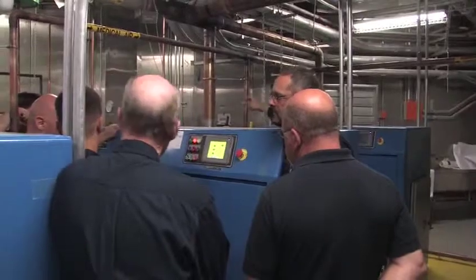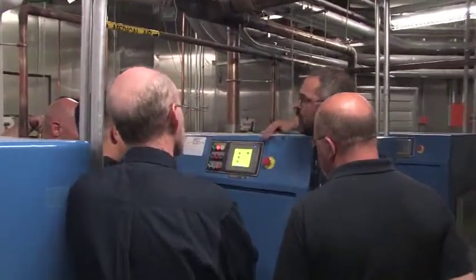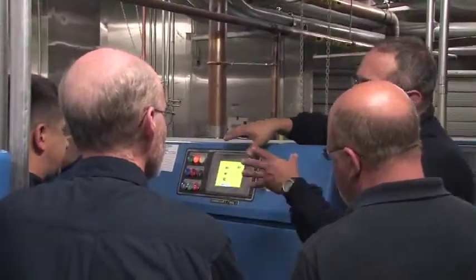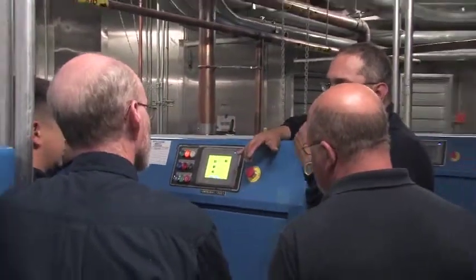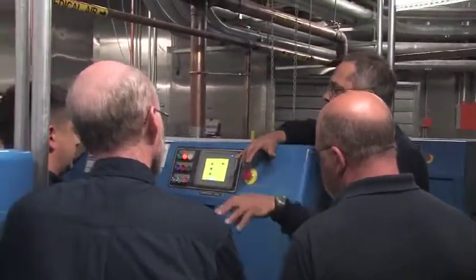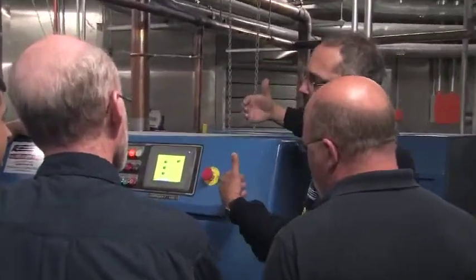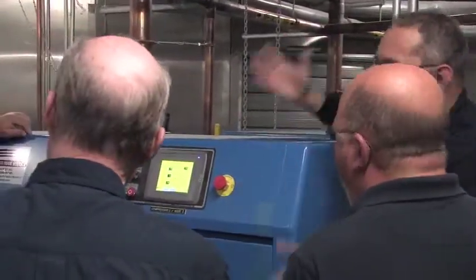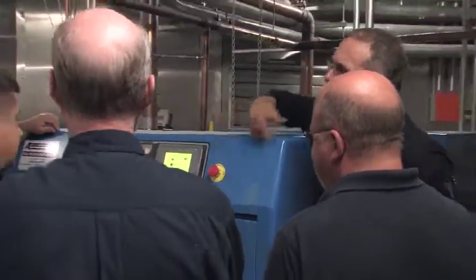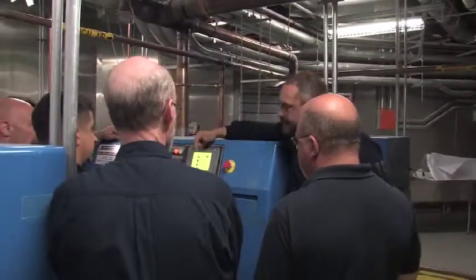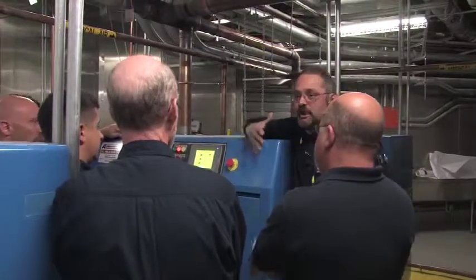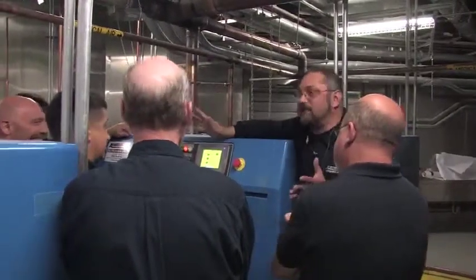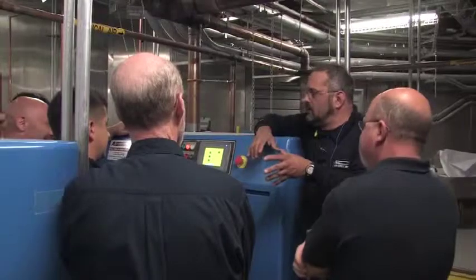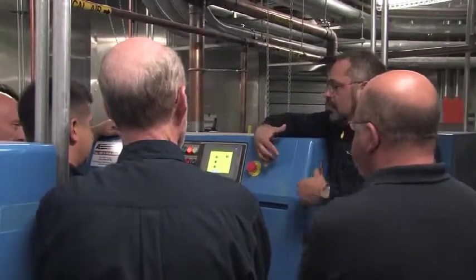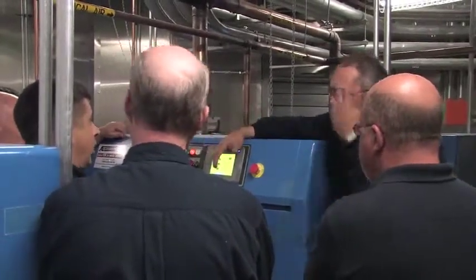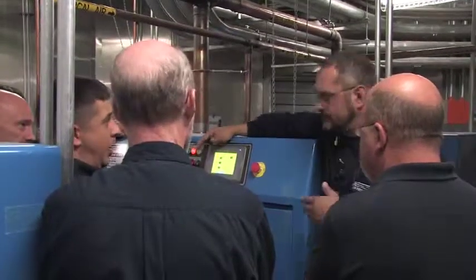Then this is all local control you're talking about right now, right? Yeah, when it's in local. In other words, by doing the lead lag that way, I fool them so that if you have any one down, when you put the other two in lead and lag, they will switch. They will be opposite, without having to spend hours going, okay, what do I want to reset it? Obviously you guys can change these, but I tried to make it so if you take them out of remote, there's something there that's going to work them in a way that you don't have to worry about. Almost like a program sequence that you've come up with for them.